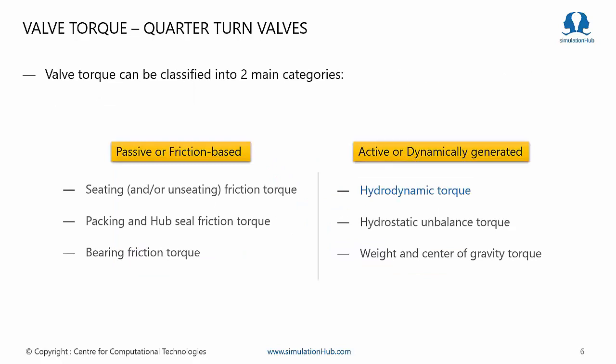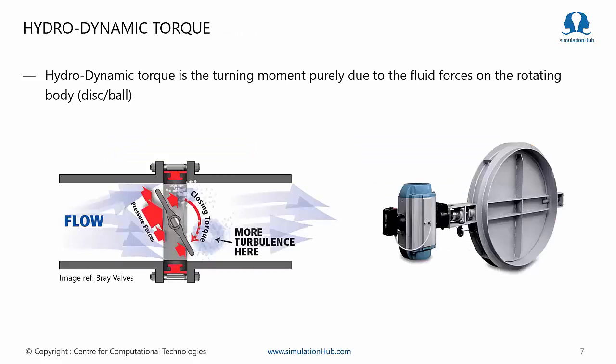Based on the type of resistance, valve torque is classified into two categories. One is friction-based, arising because the rotating body comes in contact with the seating, packing, hub, and seal. The other is dynamically generated torque, which occurs due to fluid flow. Under the dynamically generated category comes our topic of interest: hydrodynamic torque.